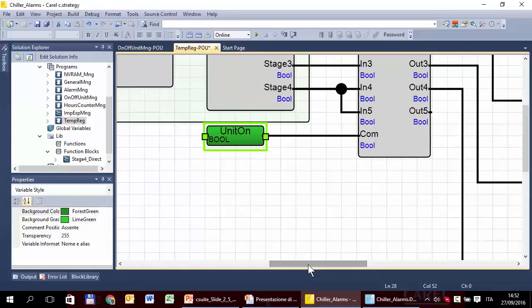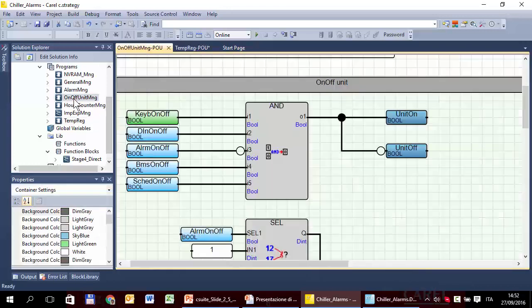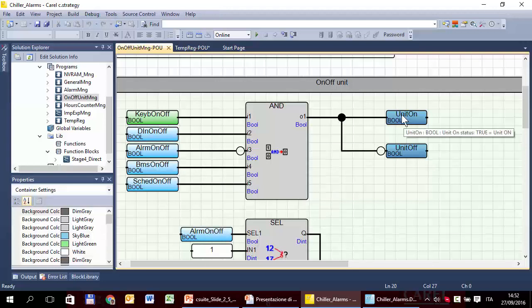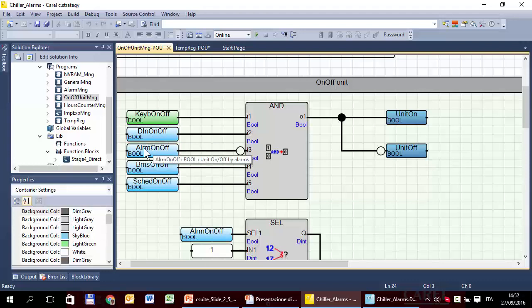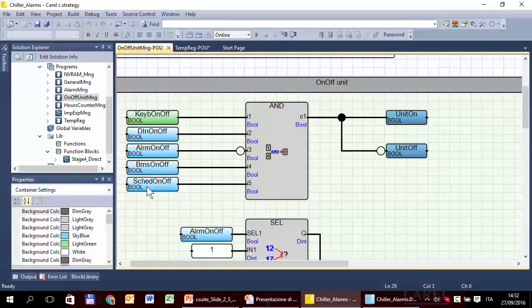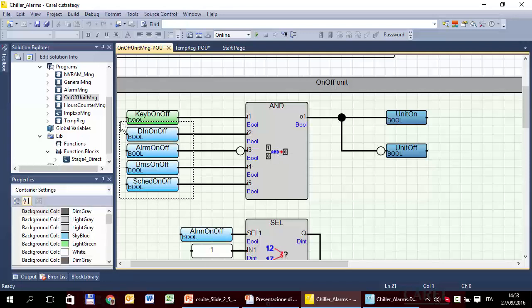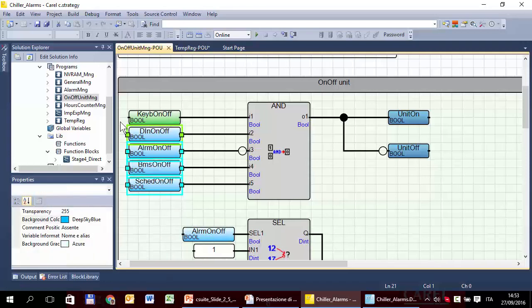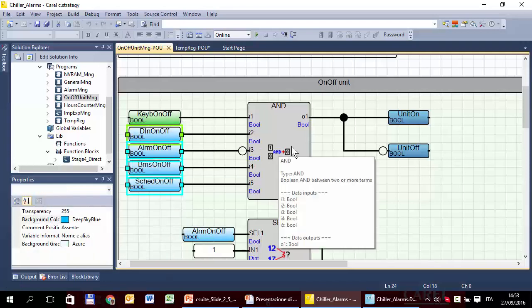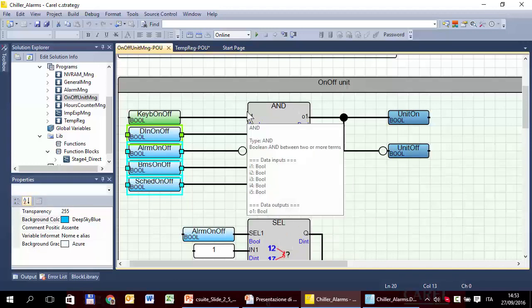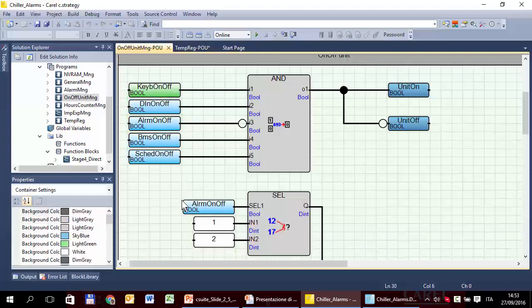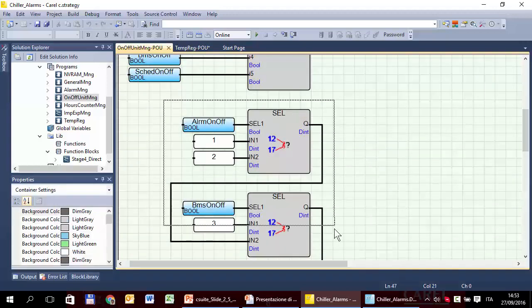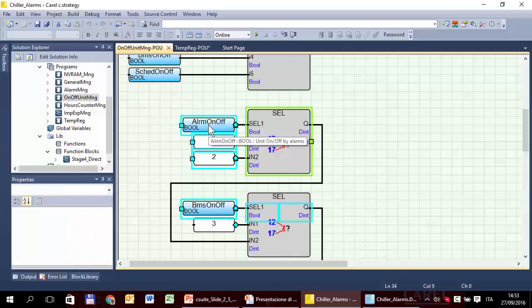Before to build, we can fix another issue that I already know, so we can save some time in this tutorial. We have to work again here because we just saw that the unit on depends not only by the on-off by keyboard, like the previous chiller project, but also according to an on-off by digital input, by alarm, by BMS, by scheduler. But in this exercise these are not used. So, we have to somehow disable this variable that must not have effect on the unit on.